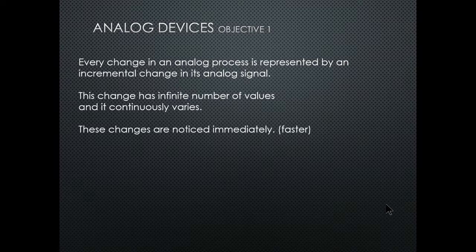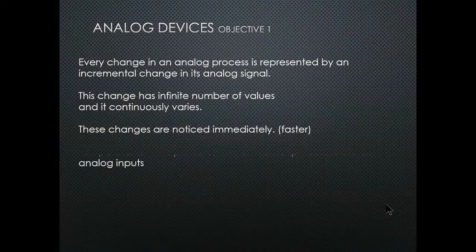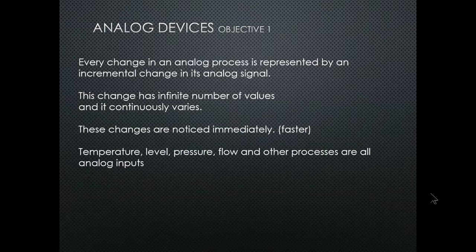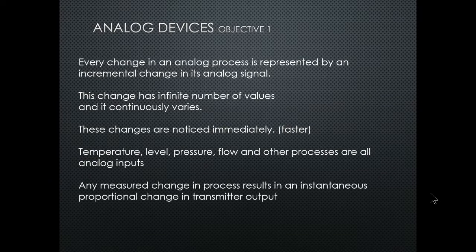In the true sense, analog is faster. Temperature, level, pressure, flow, and other processes are all analog inputs. Any measured change in a process results in an instantaneous proportional change in the transmitter output, providing that the transmitter is zeroed and spanned correctly.